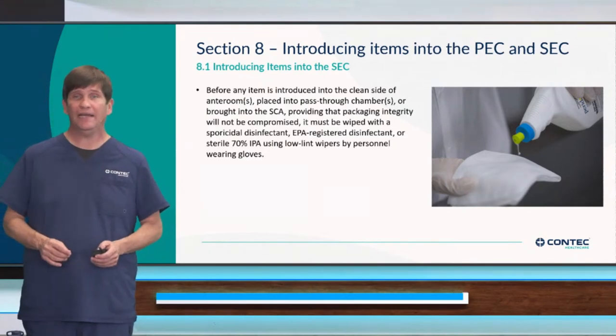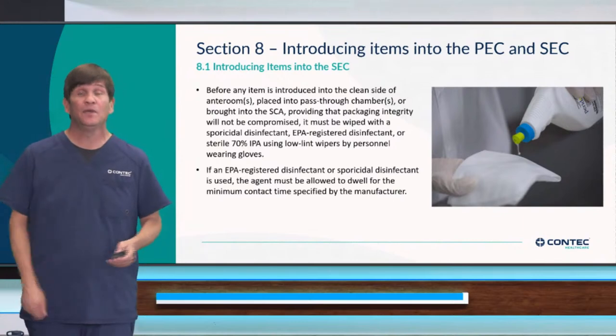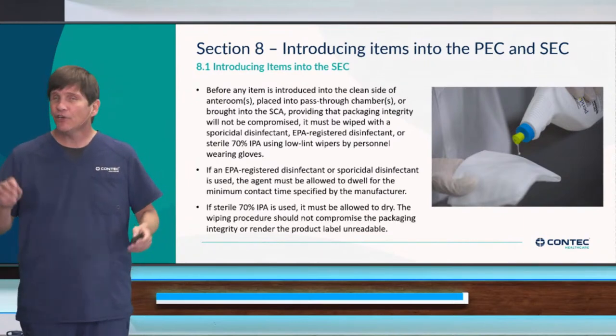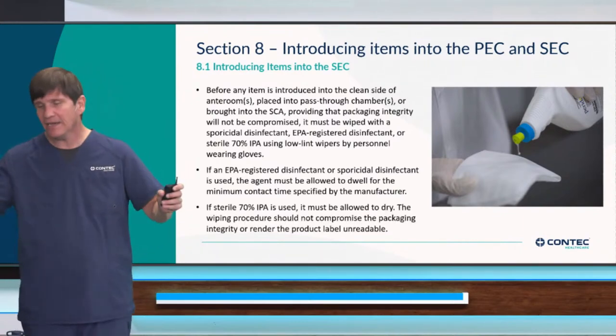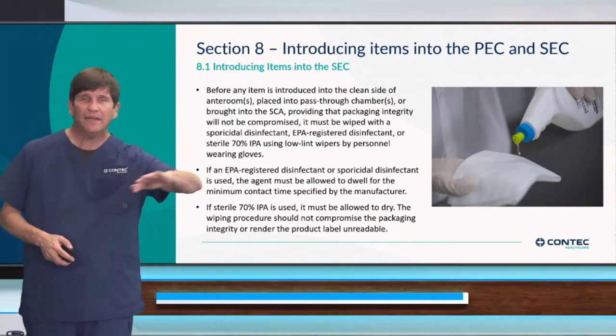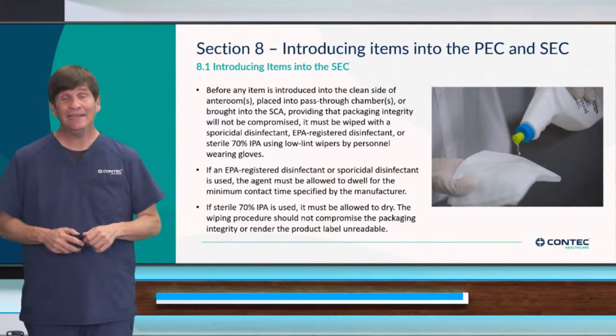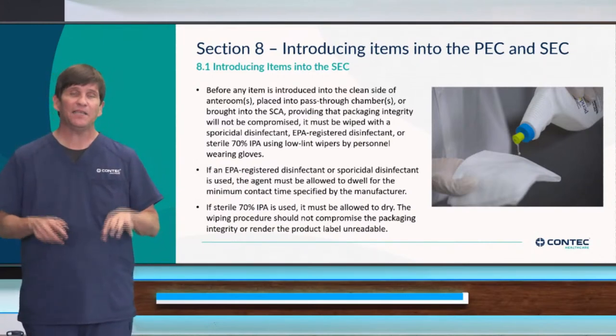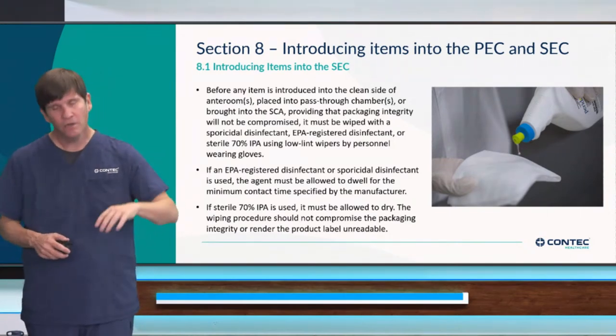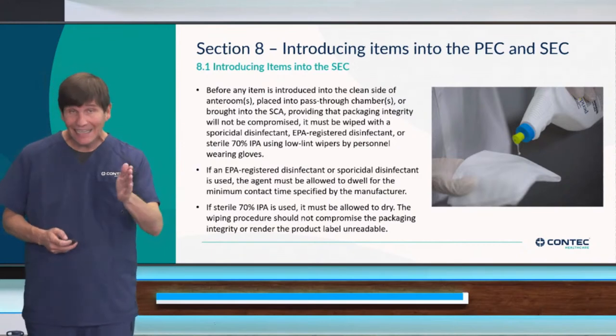I'm helping make sure I address that. You need to make sure you pay particular attention to the dwell time on whatever you're doing. And if you're only going to use alcohol, if you're not going to follow our best practice and use sterile alcohol for wiping items going into the clean room, you need to allow the sterile IPA to dry, and you need to ensure that it doesn't mess up the labeling.